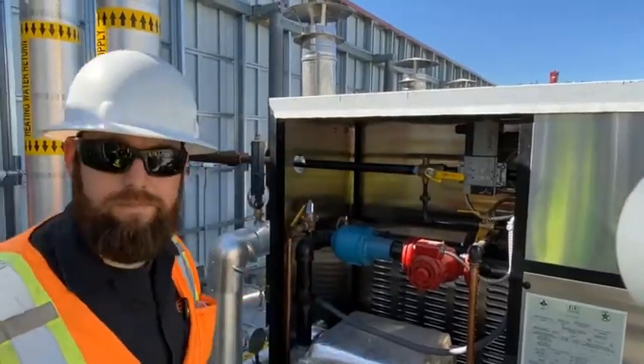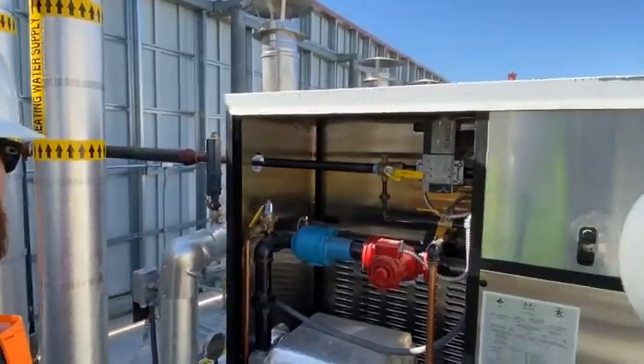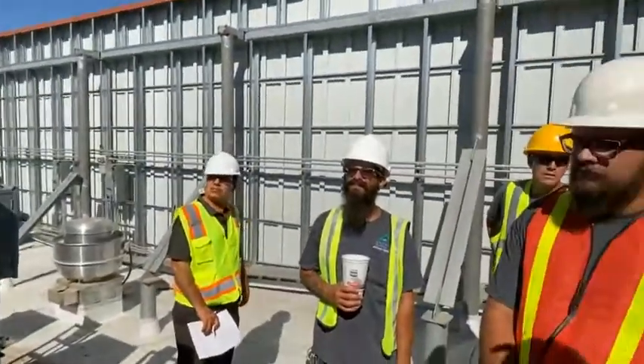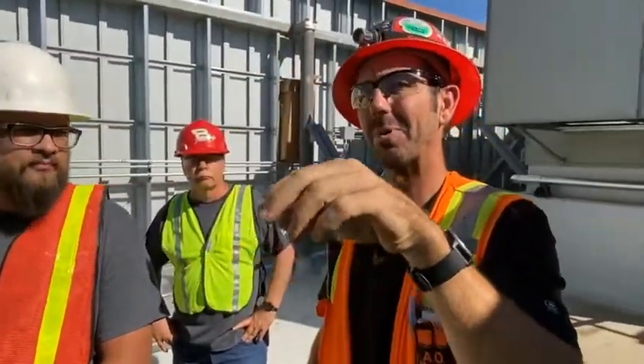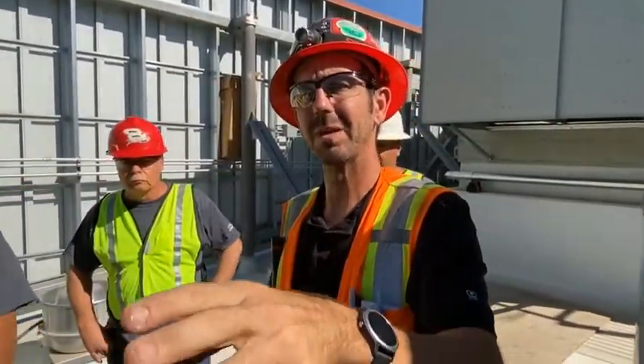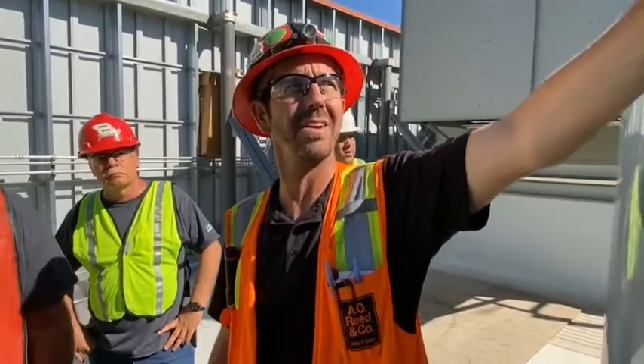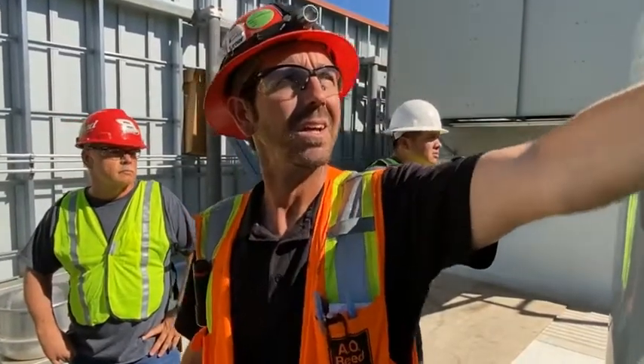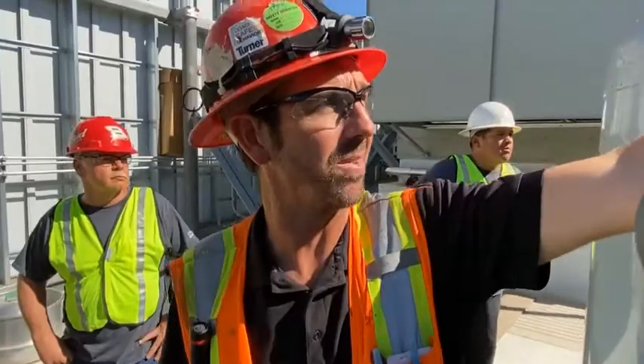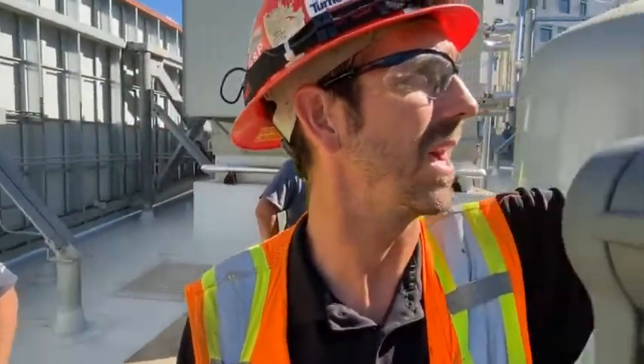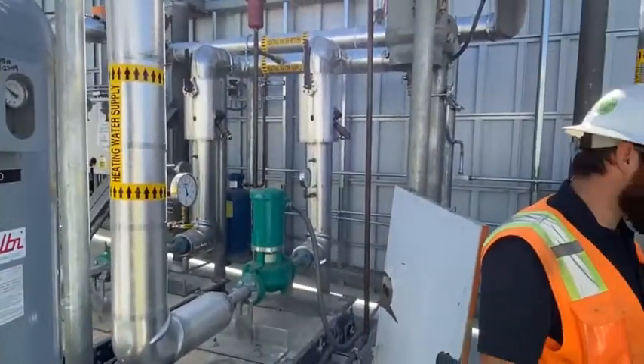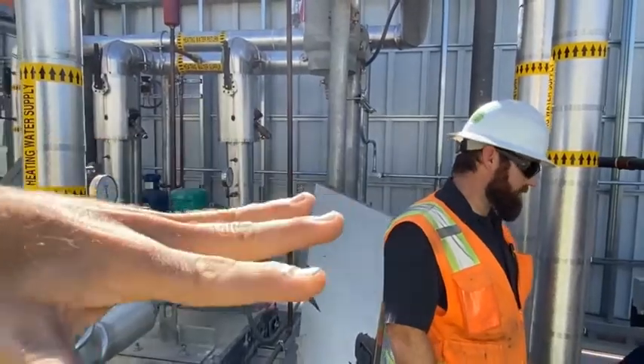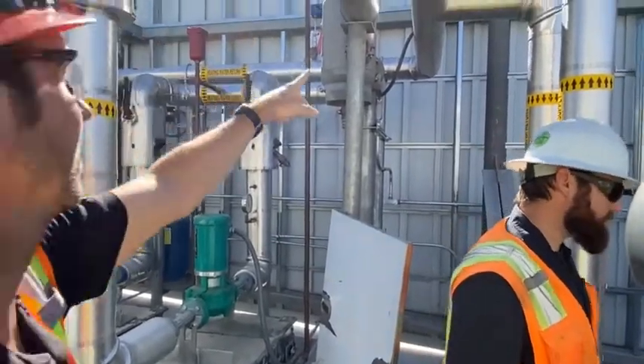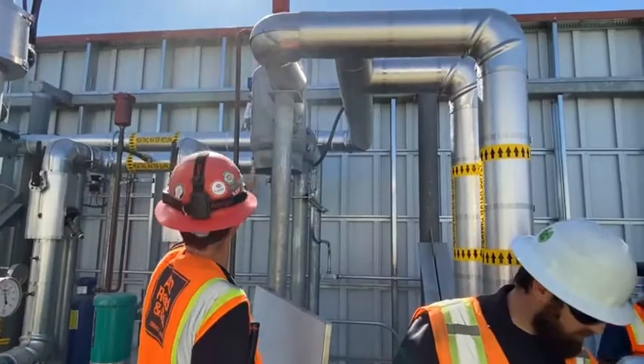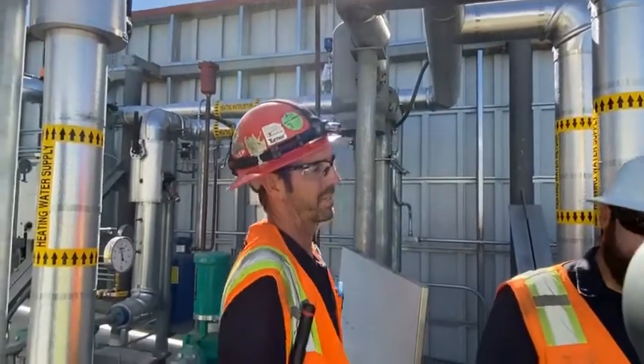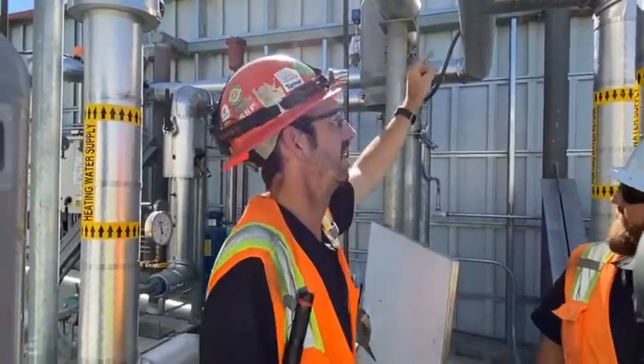So yesterday we didn't really talk about the piping system for the boilers. Since these boilers all have internal pumps, this is a primary secondary loop. The pump is pulling water out of our secondary loop that goes out to the building. So we have an air separator. The water's coming back on the upper pipe back here. It comes around the horn. It makes a turn here, as long as the boiler's not running. And it makes a turn and goes back into the pump and back out to the system, and then it comes back up that top pipe again, okay?